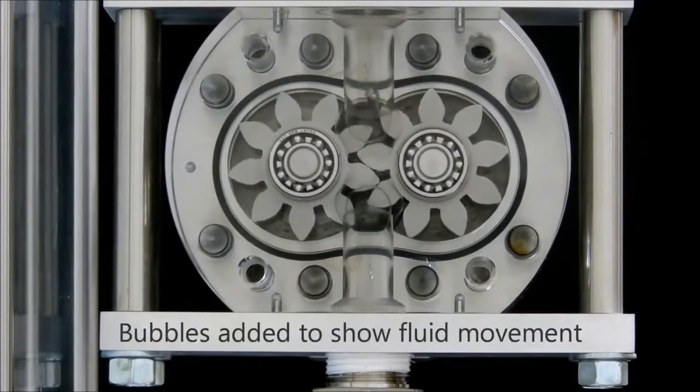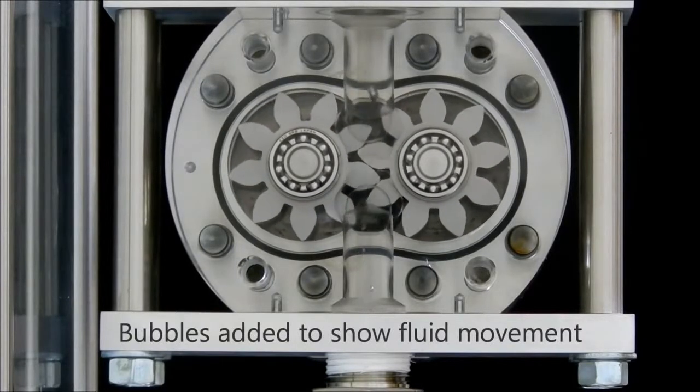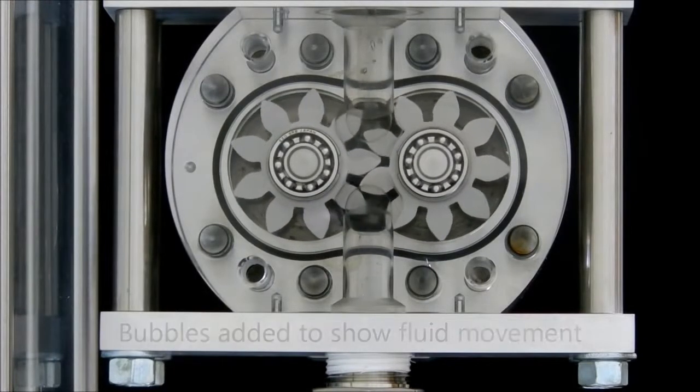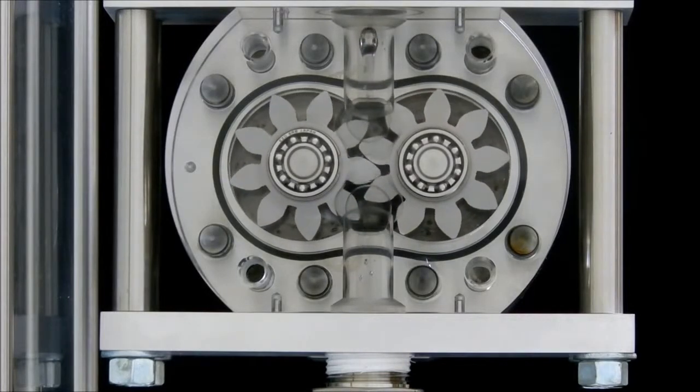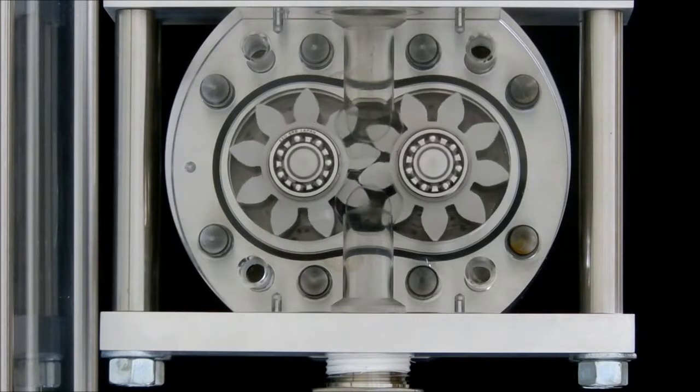As liquid pushes against the gear teeth, the gears progress and isolate a volume of fluid. As liquid continues to enter the meter, the trapped portion of fluid is carried along by the gears until the fluid is released into the downstream side of the meter.